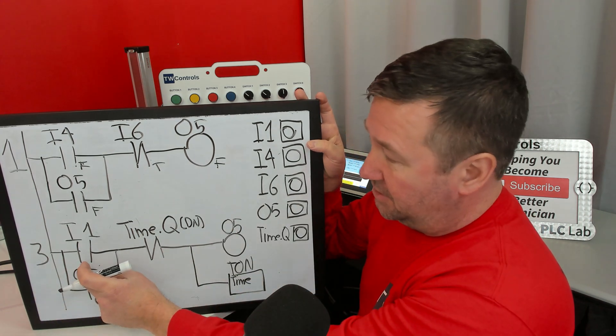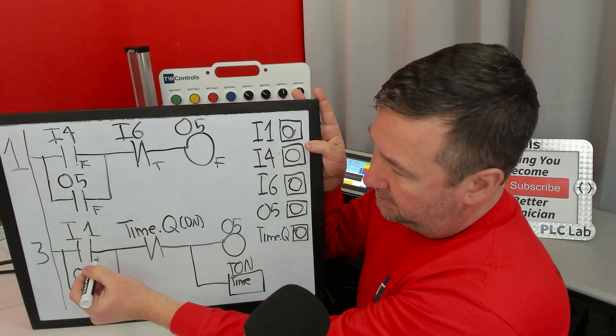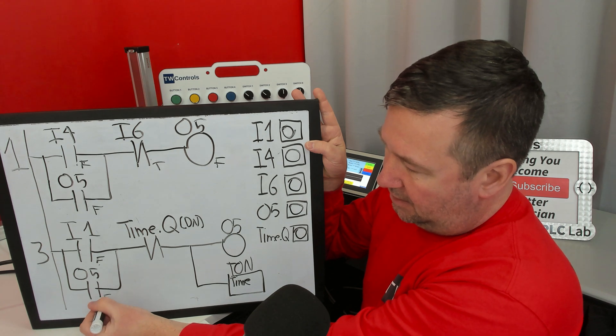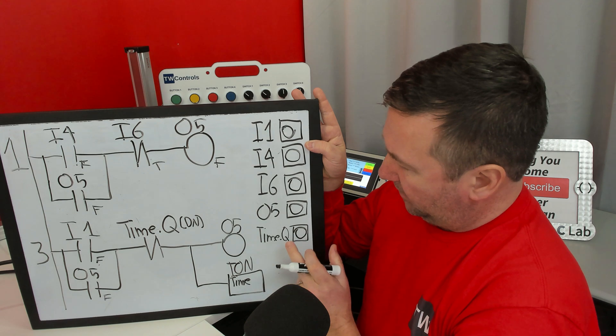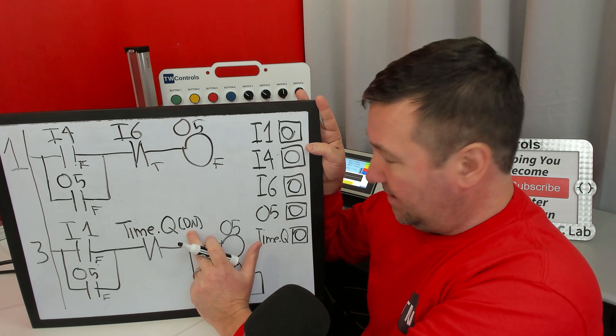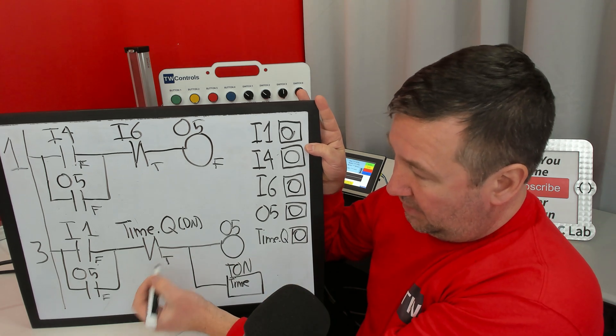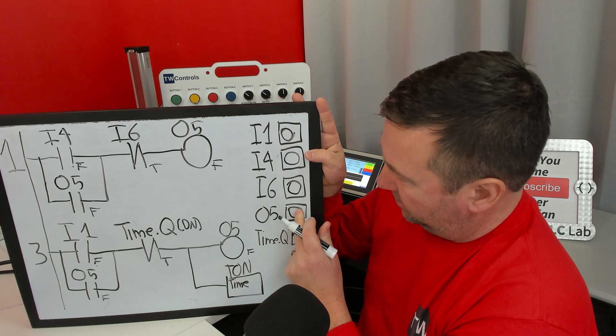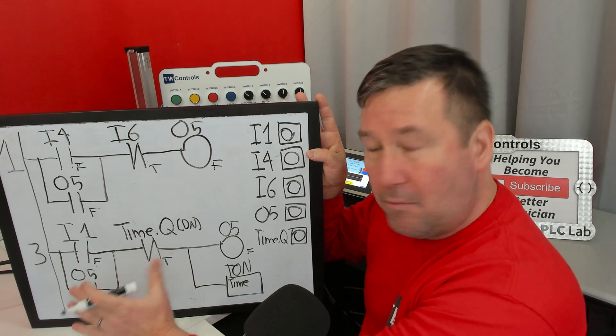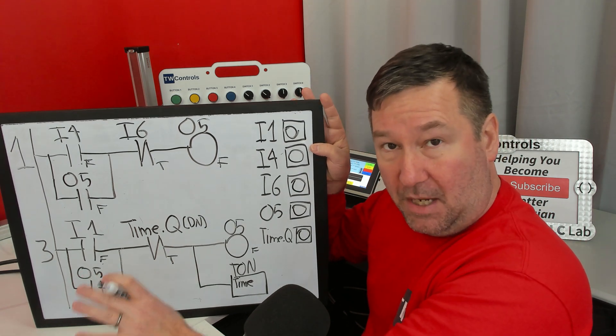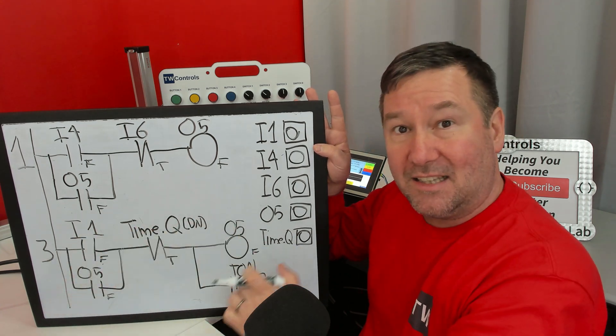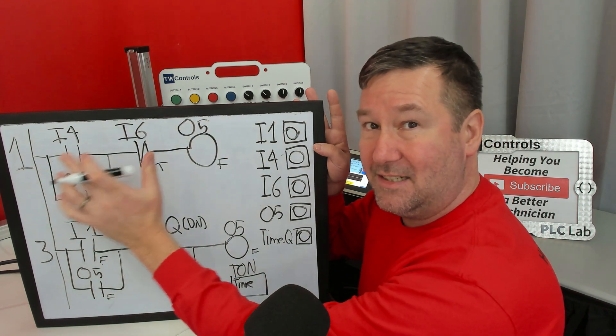Then it goes to rung 3. This instruction looks for a one - it does not have one, so it's false. Coming down, this instruction looks for a one at output 5 - it does not have one, so it is also false. This looks for a zero at the timer Q bit - in Connected Components it's a Q bit; in Studio 5000 it's a done bit. It does not have one, so it is true. But I do not have a continuous path of trues, so this will be false - writing a zero to output 5. And the false TON writes a zero to everything but the timer preset. Now for those saying the last rung wins and overwrites anything the first rung did - this will be important.